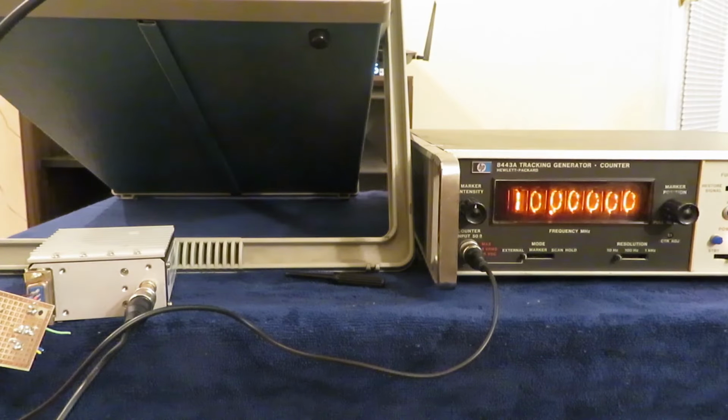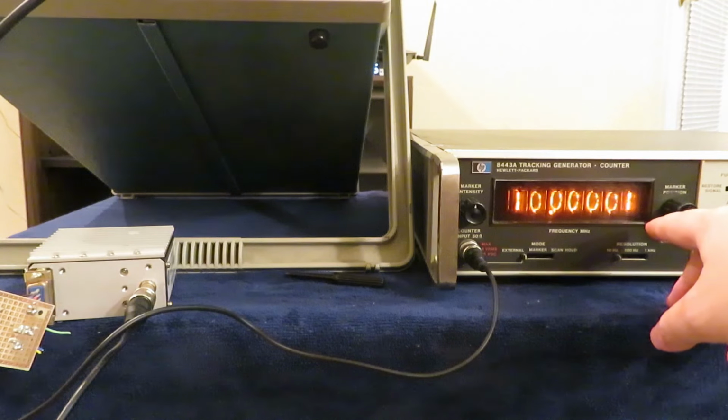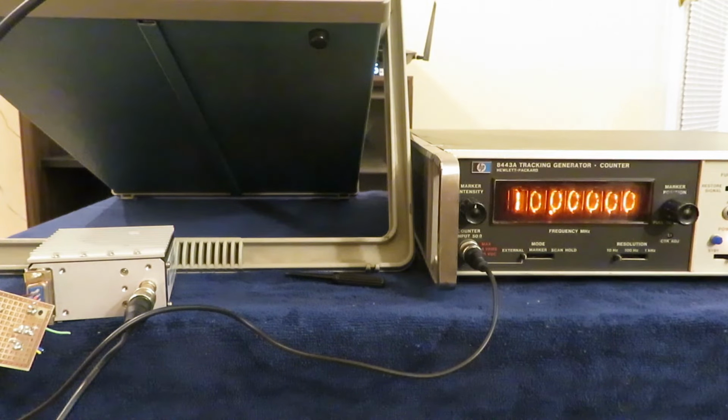So that's everything closed back up on that unit, and our frequency counter seems to be working well. You might see it flicker between all zeros and a 1 on the end. That's pretty normal. Even when a frequency counter is perfectly adjusted, you're always going to have an error of plus or minus 1 count on the last digit. So that's normal, and I think that is perfectly good in terms of the calibration.